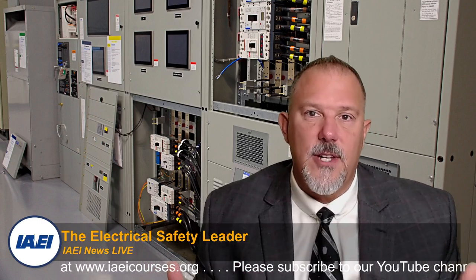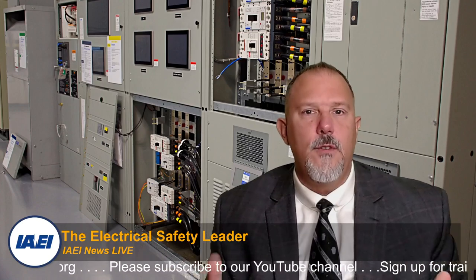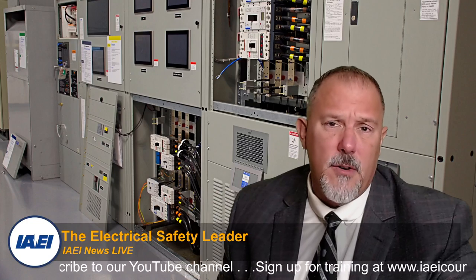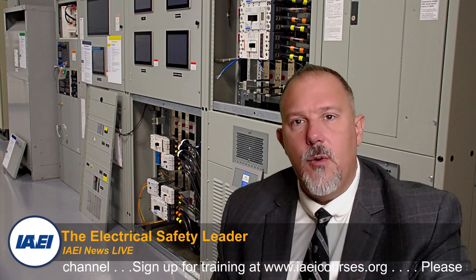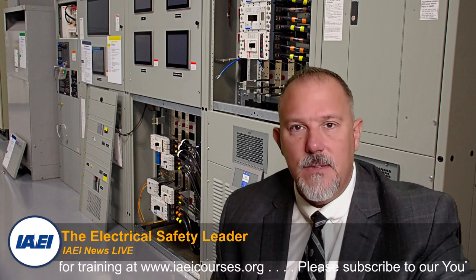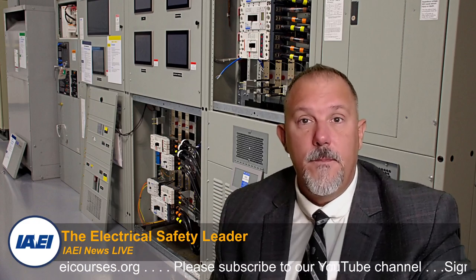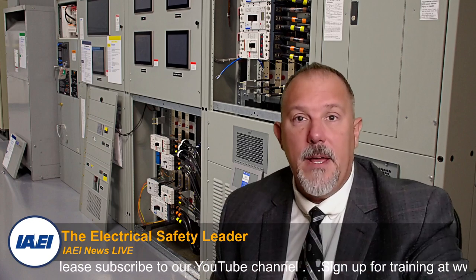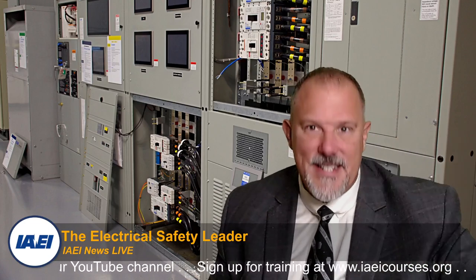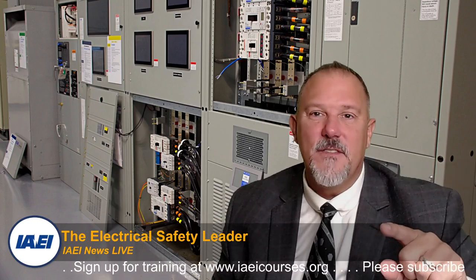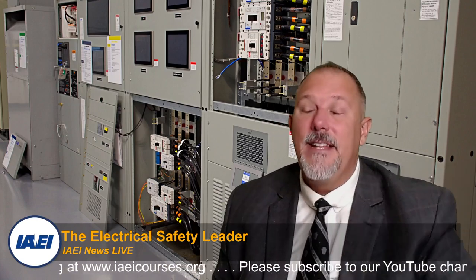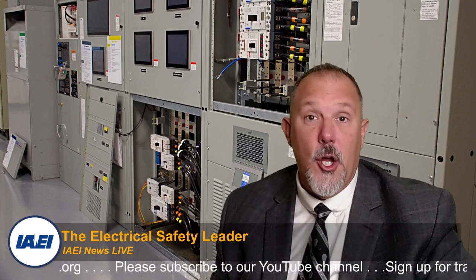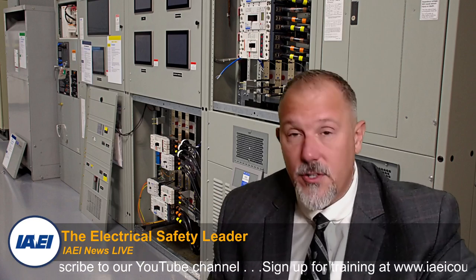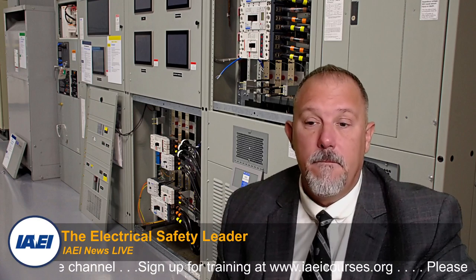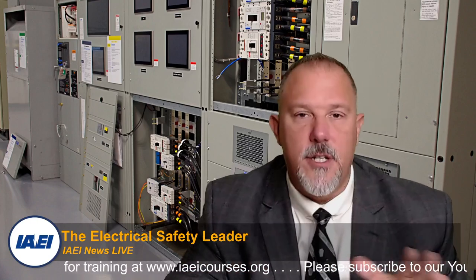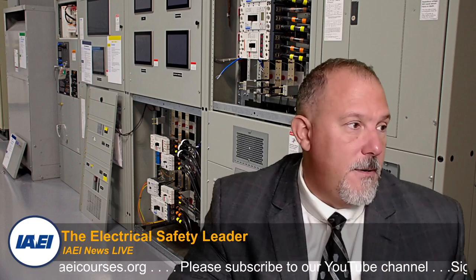Multiple utility sources, depending upon the size of the facility. There are so many different things that can occur. Double-ended switchgear, where is the tiebreaker open or closed? There are so many things you need to be aware of, the more complicated the power distribution system gets. It's very convenient when you're working on a piece of equipment, or looking at a panel board, if there's a disconnect and a raceway, and the only raceway hitting that piece of equipment is coming from that disconnect. That's a very satisfying example of knowing you are establishing an electrically safe work condition. Simple versus complex is always better for the electrical worker. And that gets you into the discussion of safety by design principles, which is maybe another session. So be aware of shock.